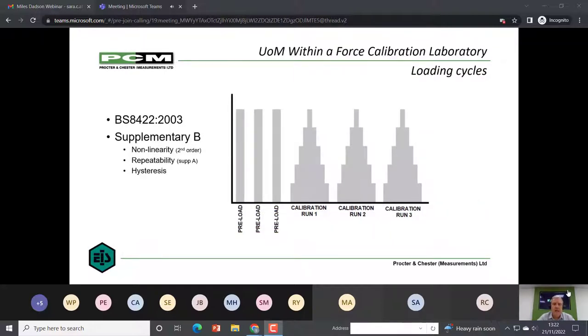Moving on, there is a supplementary B calibration, which differs from the standard calibration, in which you have no rotation. You just conduct three calibration cycles after the three preloads. This again will give you a non-linearity, second order regression. It can offer you a repeatability, not a reproducibility, but more importantly, it offers you a hysteresis.